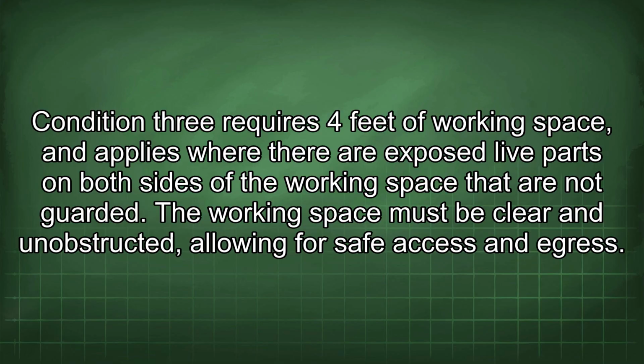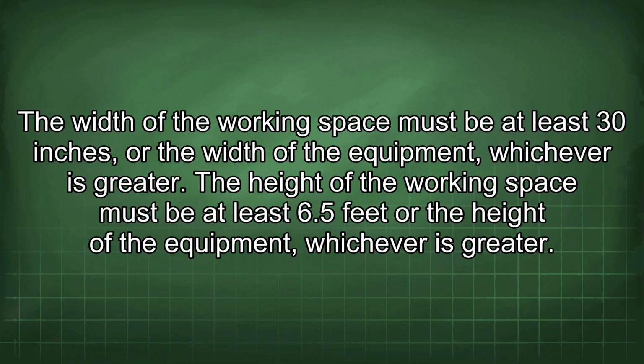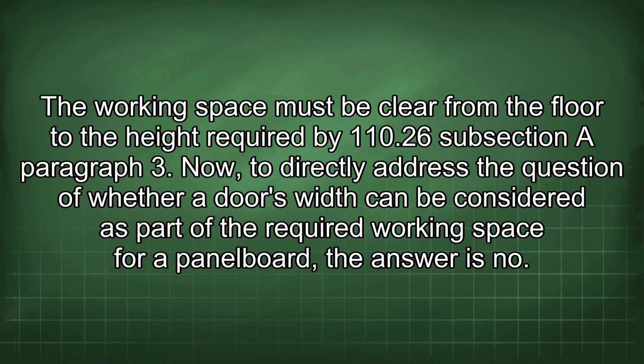The working space must be clear and unobstructed, allowing for safe access and egress. The width of the working space must be at least 30 inches, or the width of the equipment, whichever is greater. The height of the working space must be at least 6.5 feet, or the height of the equipment, whichever is greater. The working space must be clear from the floor to the height required by 110.26, subsection A, paragraph 3. Now, to directly address the question of whether a door's width can be considered as part of the required working space for a panel board, the answer is no.